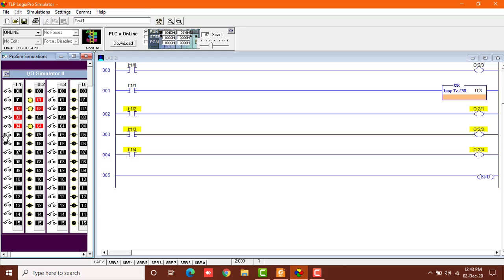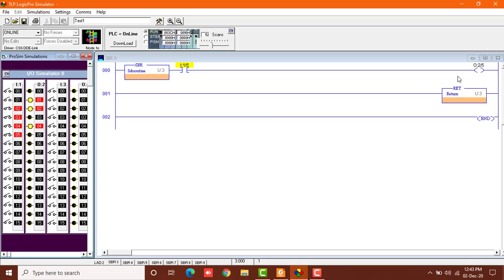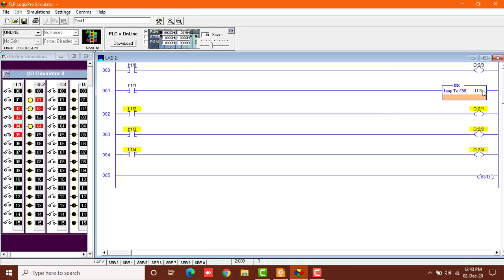But you can remember that in this subroutine 3 we have placed input 1 slash 5 button to the output 2 slash 5. So what will happen if I turn this on? The output 2 slash 5 is not turning on. Why? Because I have not sent the power to this subroutine U colon 3. Only when I'll turn this rung condition to be true, which is for the subroutine 3, only then the output 5 will glow if the input section 5 is turned on.